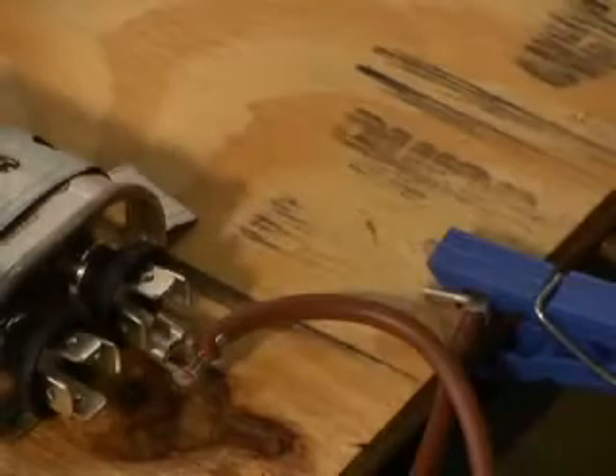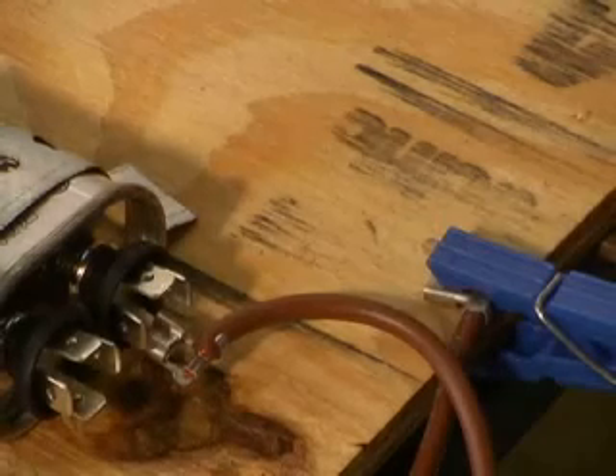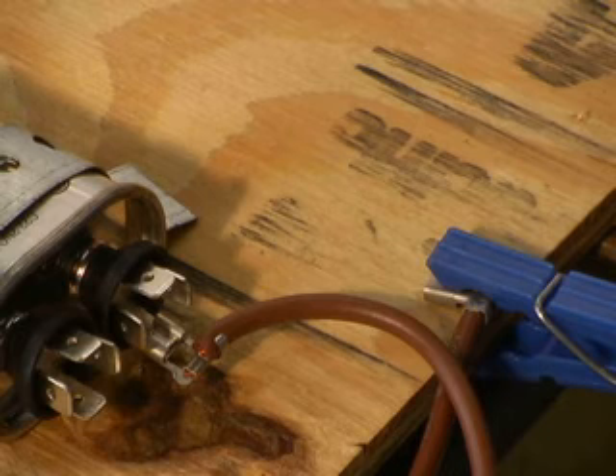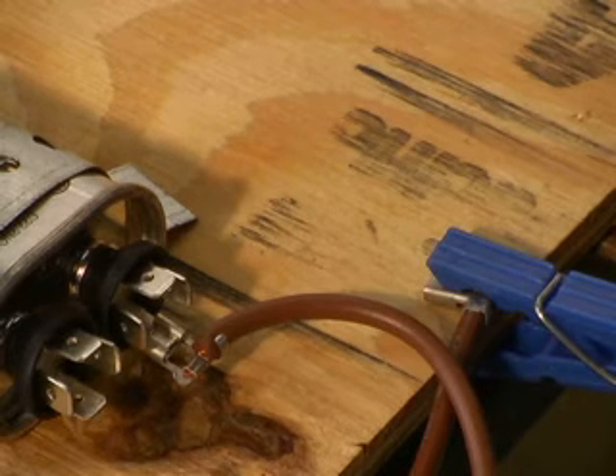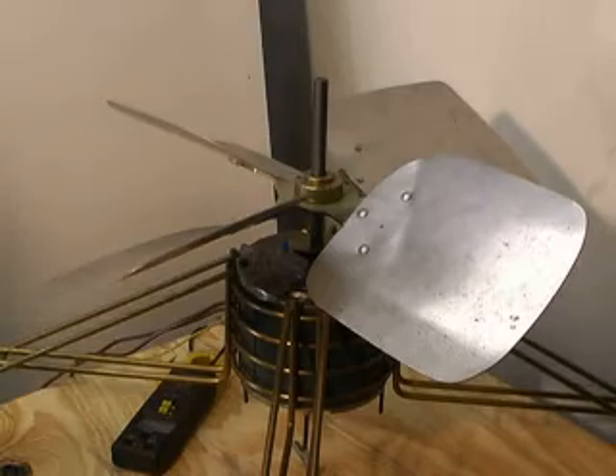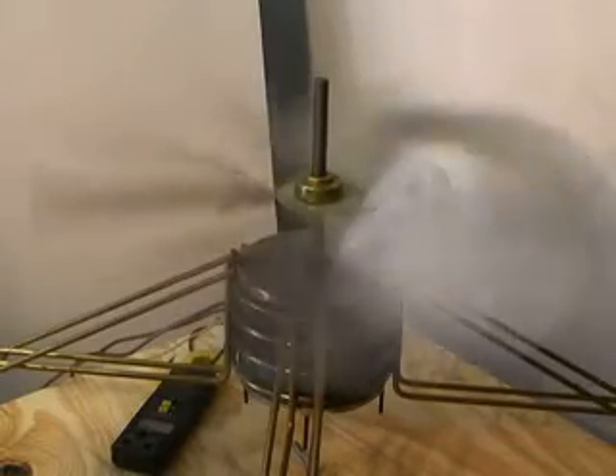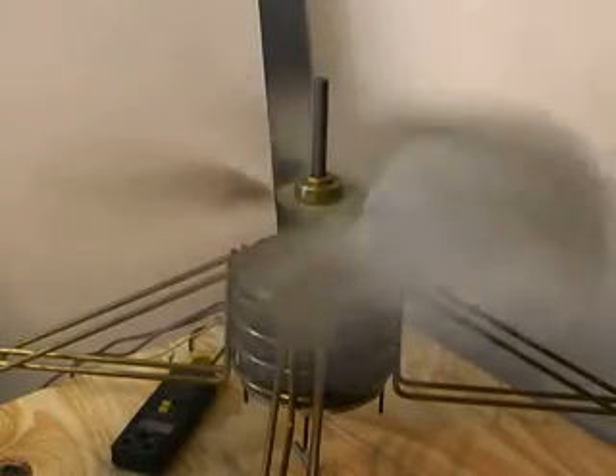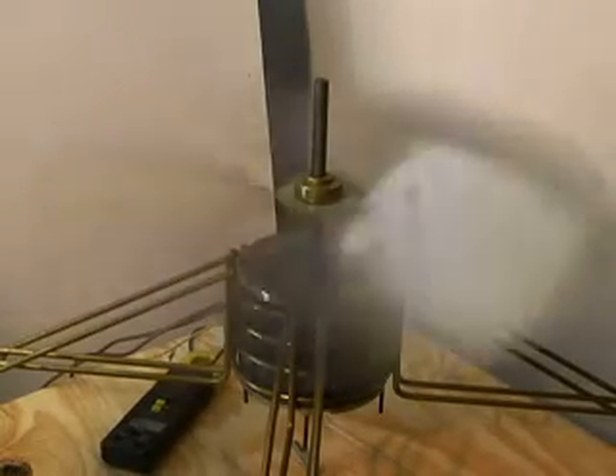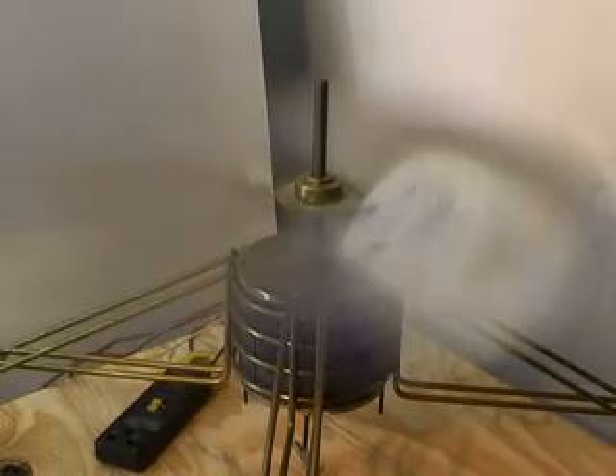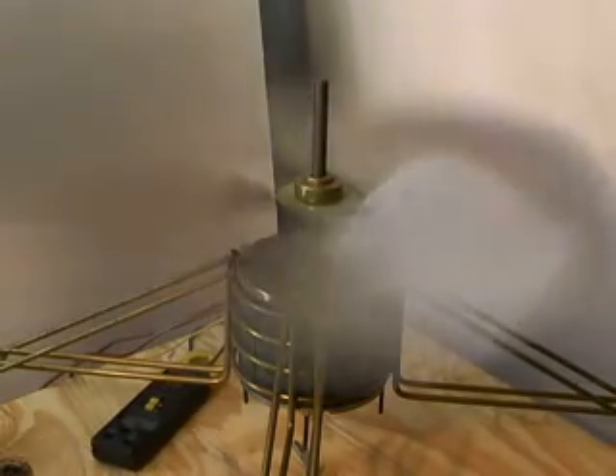Okay, now we'll simulate an open run capacitor. I just disconnected one of the wires, and we'll energize the thing now and see what it looks like. So it's just sitting there humming. You can spin it, and it'll take off, which is fairly characteristic of capacitor problems. Sometimes the blower will start up and run without any help when the capacitor's bad, but a lot of times they won't, and you can spin it and it'll run, and it seems to be running.